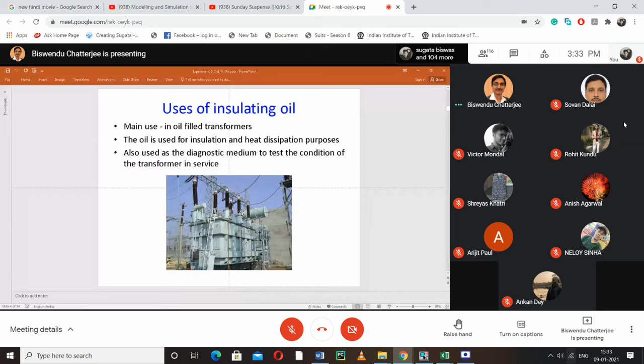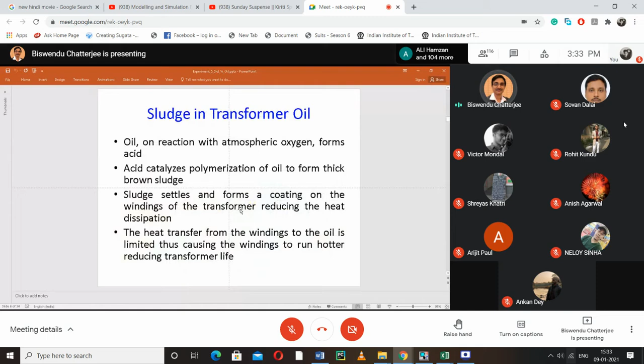Now tell me, this is a huge transformer that you have seen. I have already shown the picture. Here was one picture, this one. This huge transformer, if I fill the oil up to the brim totally and transfer it, in your common sense, you can see the oil can spill. So before transporting, some oil is removed and the rest of the oil is filled after the transformer is transported. Now suppose in a very cold region like Kashmir, we want to pour the oil in the transformer during commissioning. What will happen? If the temperature is below pour point, it will be solid and you need a heating arrangement. So here is the significance.